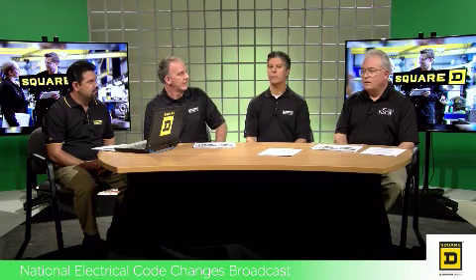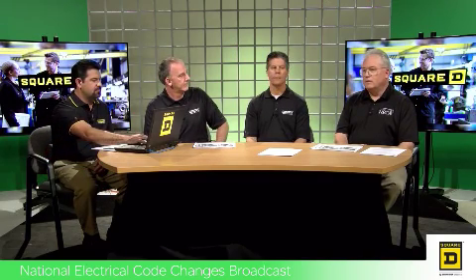Great points, Alan. I think that, once again, this is not something new being introduced to the industry. This is ongoing. Typically with medium and high voltage systems, equipment, and applications, you usually have performance tests and verification that systems are going to operate as intended when they're energized. What this does for the inspection community as well is give them another basis for approvals, by requiring these tests and performance criteria to be documented in a way that they can use in addition to their inspection while they're looking at approvals to energize this equipment.